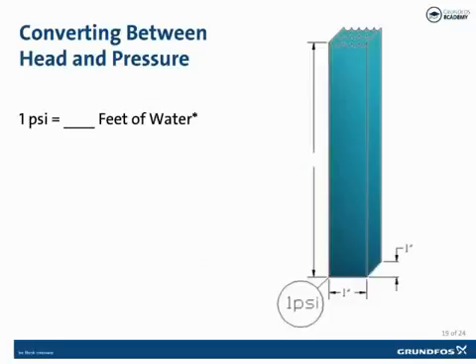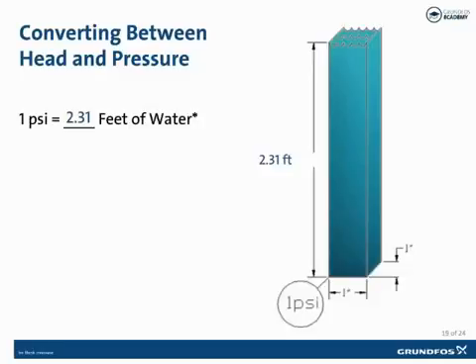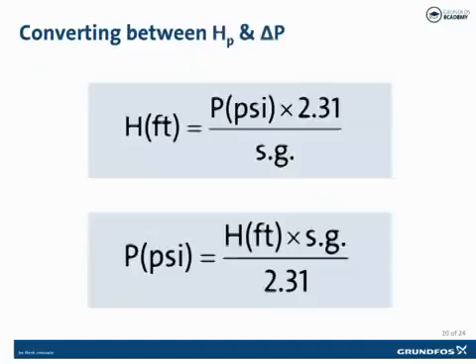The second component of calculating total dynamic head is pressure. Since centrifugal pumps are not rated in PSI but rated in feet of head, we need to convert from PSI to feet of head. In the example shown here, we have a tube that is one inch by one inch, which is one square inch. In order to read one PSI at the bottom of this tube, we would have to fill the column with water to an elevation of 2.31 feet tall. Therefore, the conversion for water between 32 and 60 degrees Fahrenheit is: one PSI equals 2.31 feet of head. The formula is PSI times 2.31 divided by the specific gravity of the fluid to get feet of head.